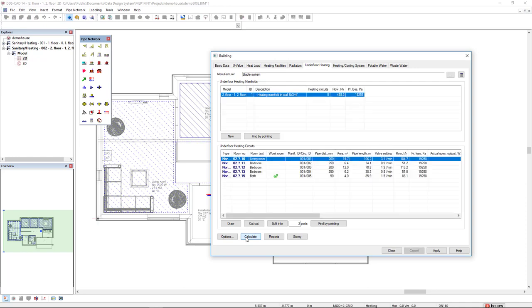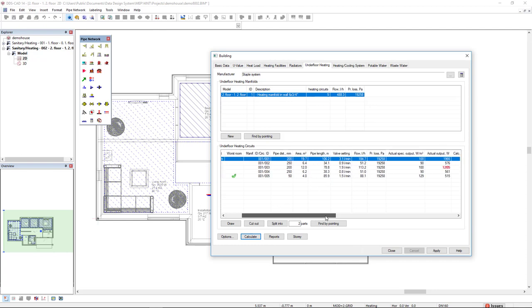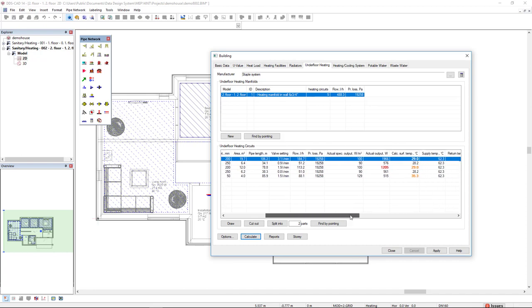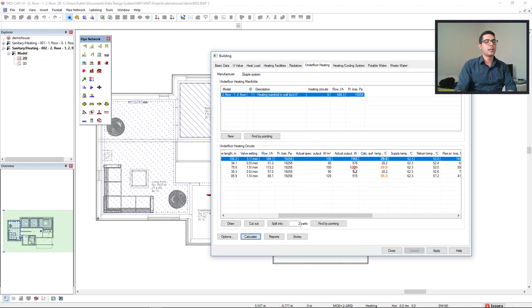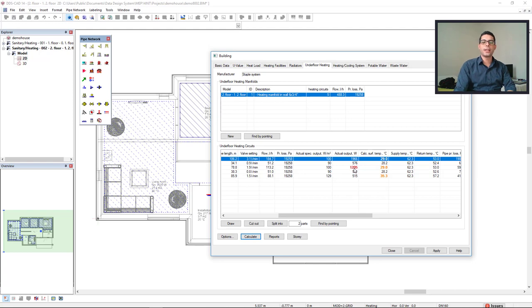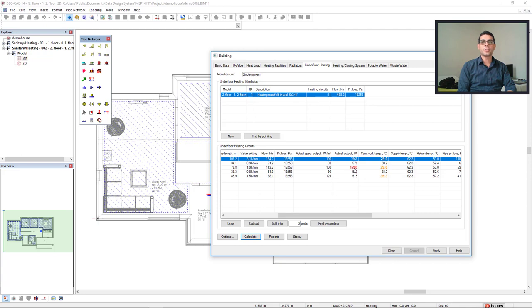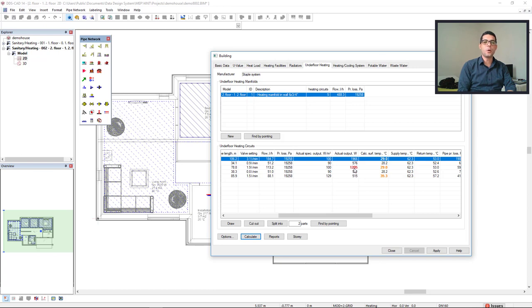We see here some important information in the column pipe distance, and we can also see the pipe length. If we move to the right, we can see the actual output. We see in red the indication that the actual output is not enough for the target output of this room. One possibility would be to optimize the system, or in another case, to use an additional heating facility.